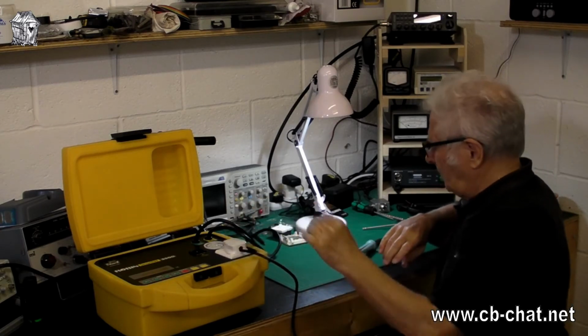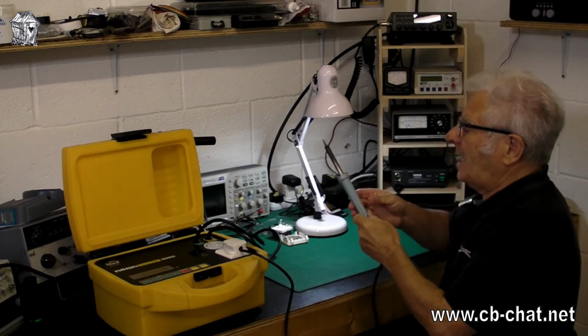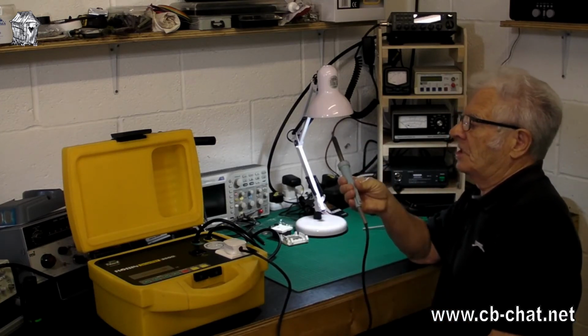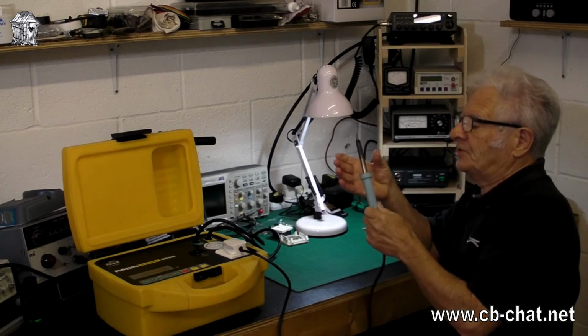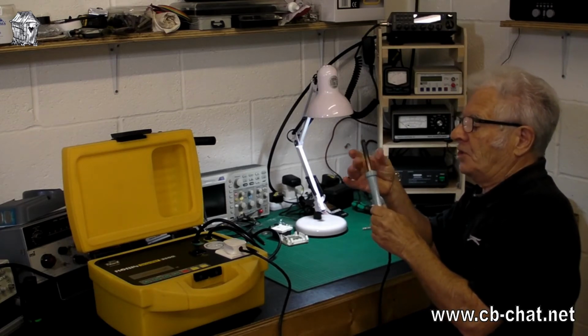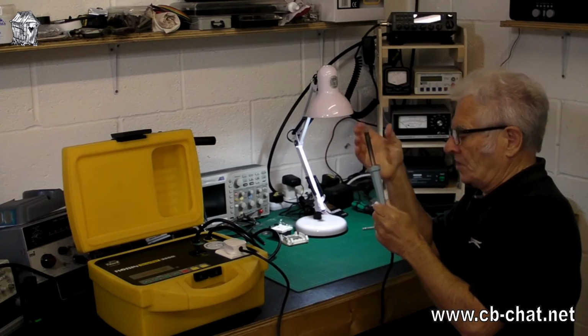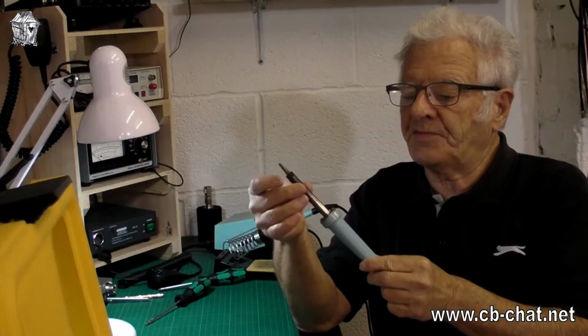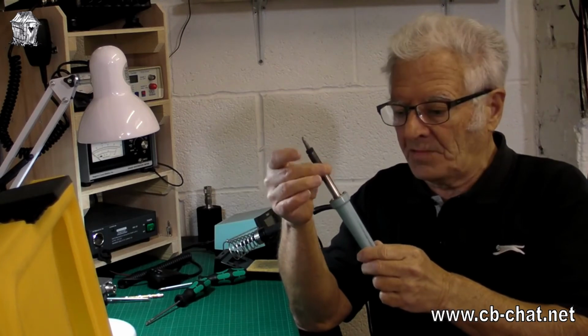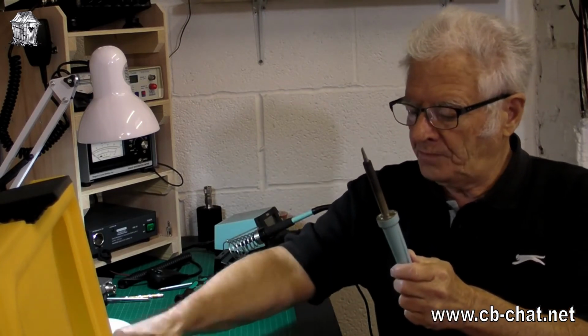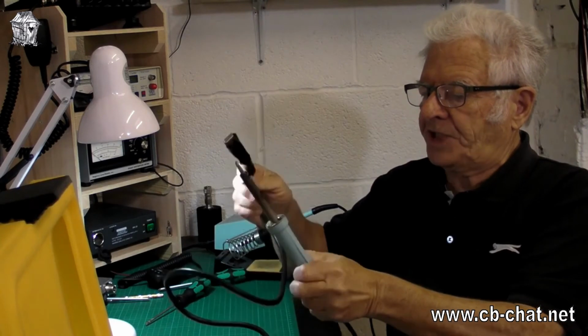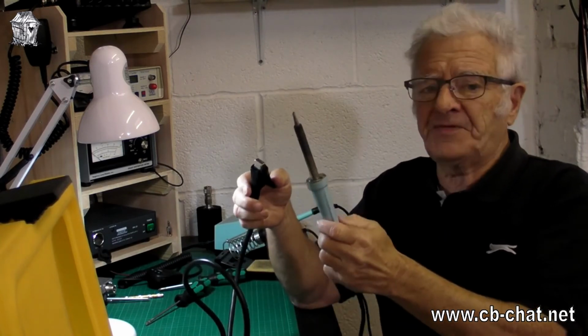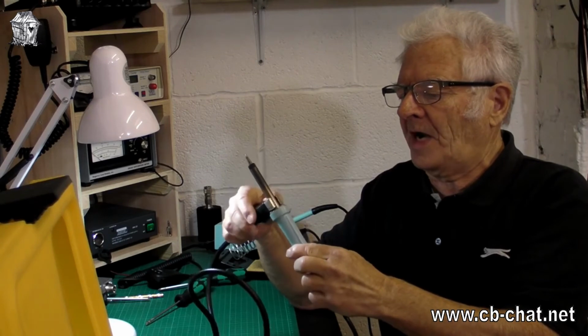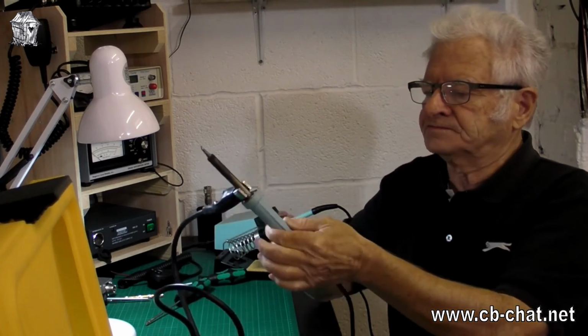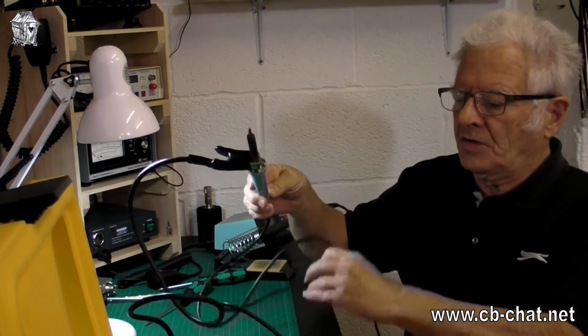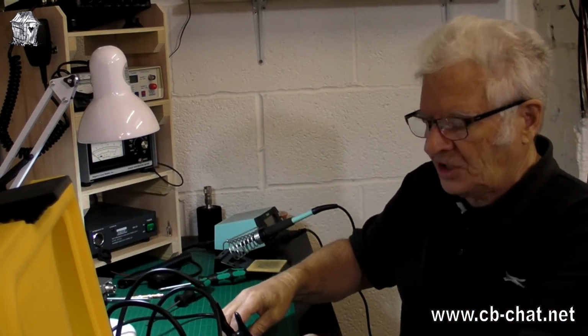It's nice and firm. Now if the item has got any metal parts, you're supposed to test to make sure that it's earthed. There's no power on this, so it's not going to get hot, don't worry. But we've got to make sure that this metal part is not going to become live. So you put a probe on it with this tester. Different testers have different kinds of probes, but there we are. Good old crocodile clip on it. So now we can proceed with the tests with the machine.